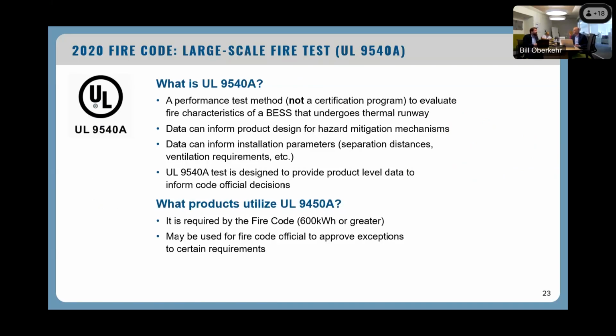It's not a certification, it's a test method. That test method produces a 9540A report. Folks like ESRG and DNV and others are intentionally setting these systems on fire, initiating thermal runaway, to record what happens so we have some idea of how these systems will behave in the built environment. So that's what the 9540A test is: a list of data that tells us how the system behaves in a failure condition.